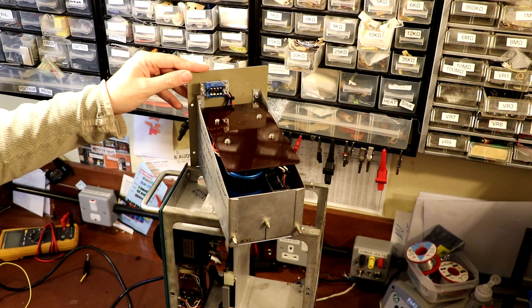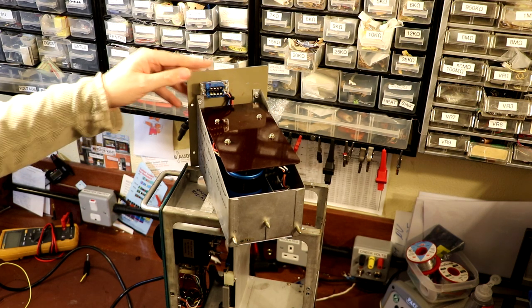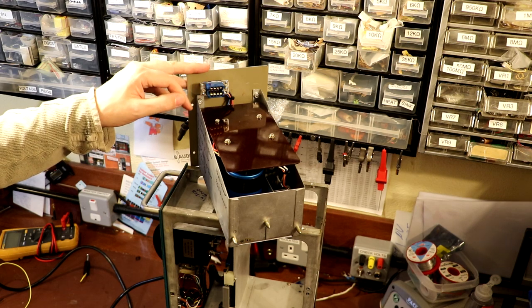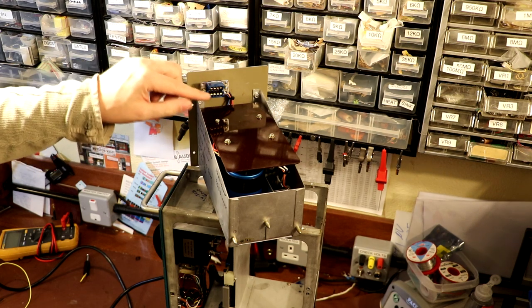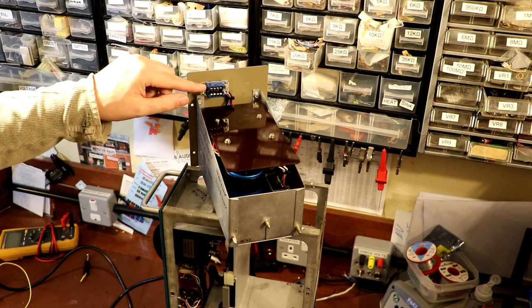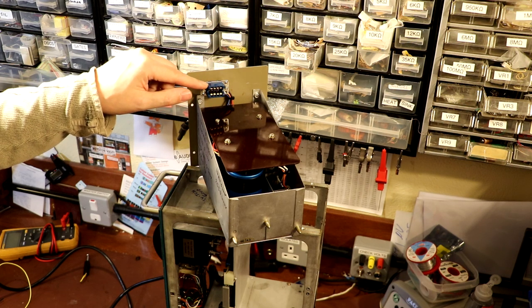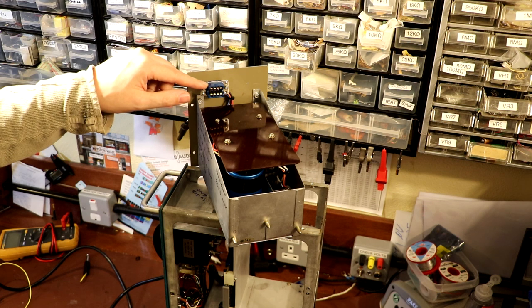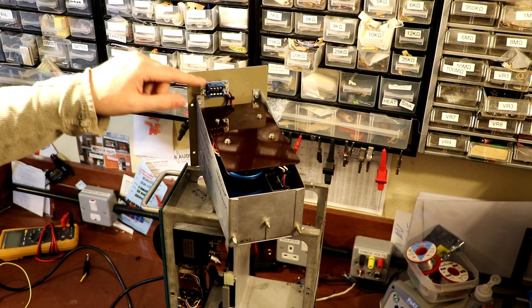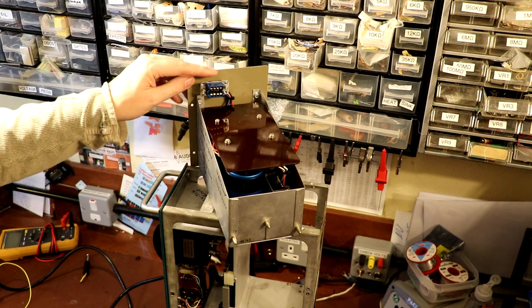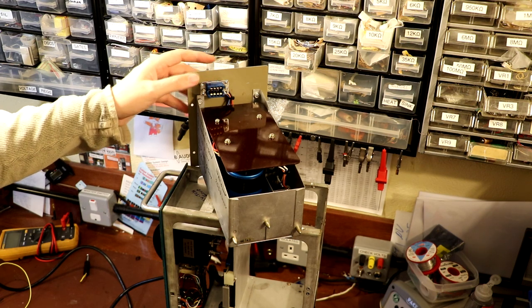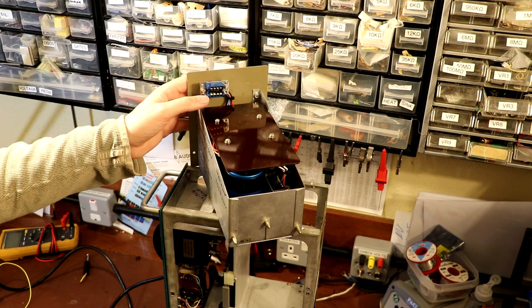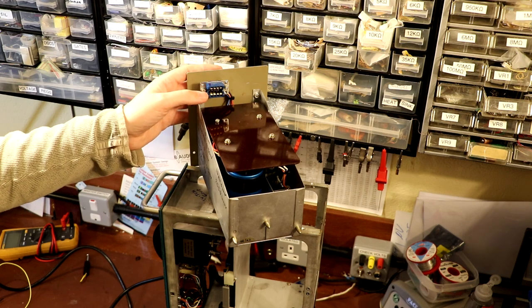the power supply. It's not that it was tripping out the earth leakage, it just couldn't get any power to it. And I've done some tracing round, and what I think the problem was is one of these pins here connects from the live mains supply, and it goes to the switch on the front of the piece of equipment and then comes back. So unless you have these links in place, the power supply won't actually power up. Now it should have worked, but I think what the problem was, some of these pins were slightly bent back.